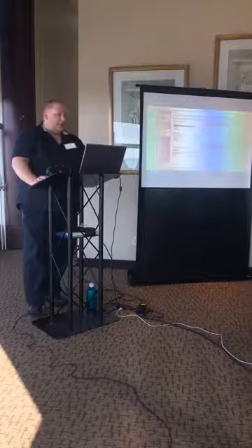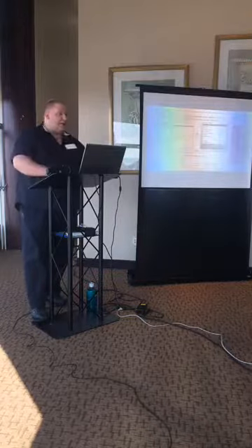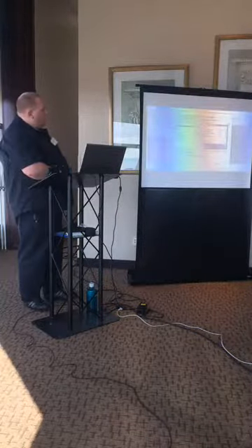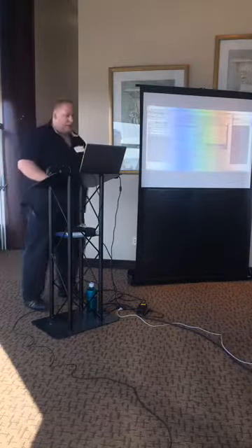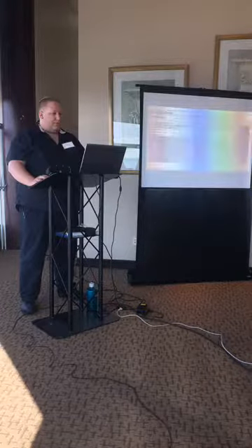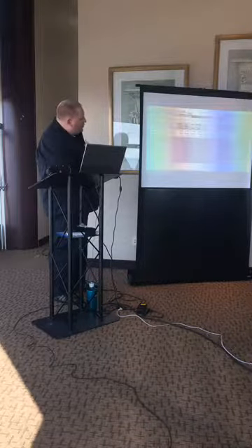What this does is it tells you that the equivalent orifice diameter is the orifice diameter that you would need based upon a sharp-edged orifice with a discharge coefficient of 0.6. So we can see that if we're going to use an orifice, that's our diameter that we need.